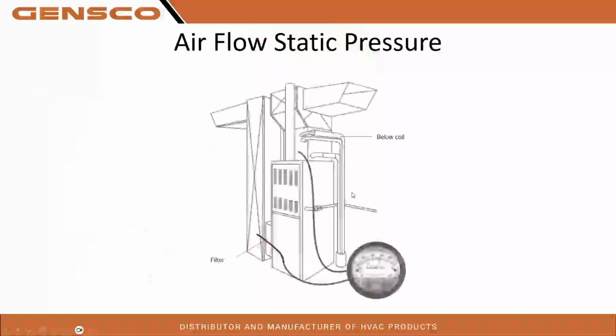Something to think about. Airflow and static pressure. So gas furnaces, we're actually going to go after the filter, and then we are going to go below the coil. So we don't care what it's after the coil. We want to know before the coil for airflow static pressure.